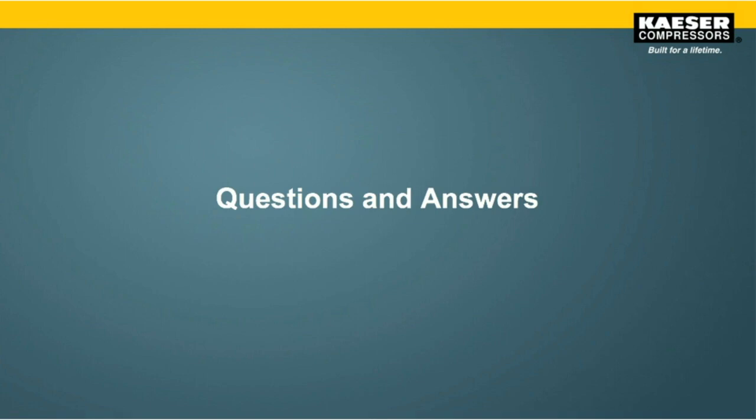Hi, so this is Grayson Atkinson. That's actually a really good question, and there's a lot that could go into that. You could have potentially a problem with the machine. It could be that something isn't operating the way it was designed to. You might have a clogged cooler. There could be something wrong with the internals of the machine that are limiting the airflow and the cooling. But more than likely, it's something wrong with the room.